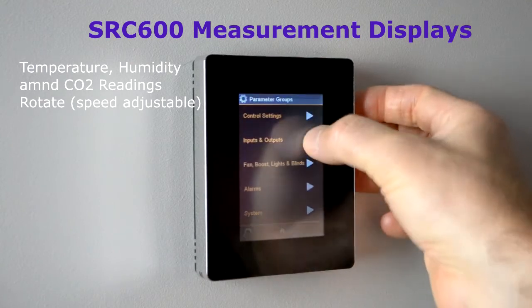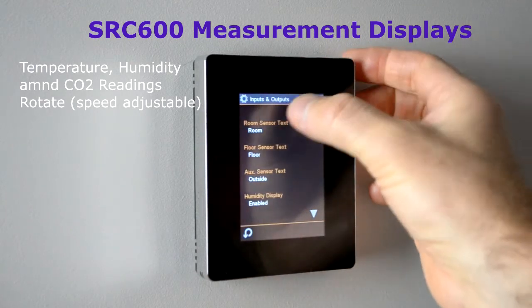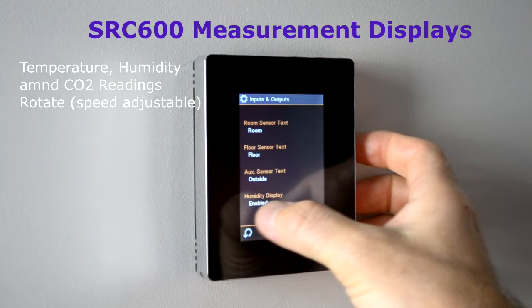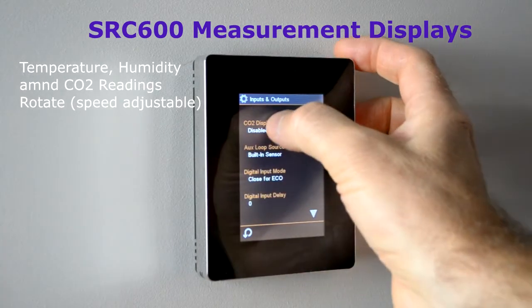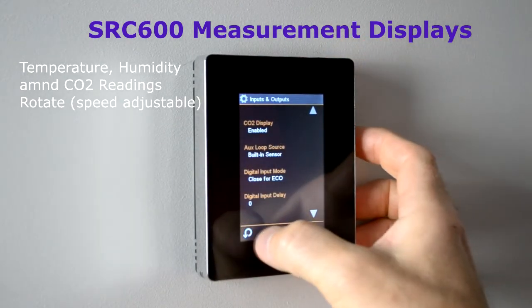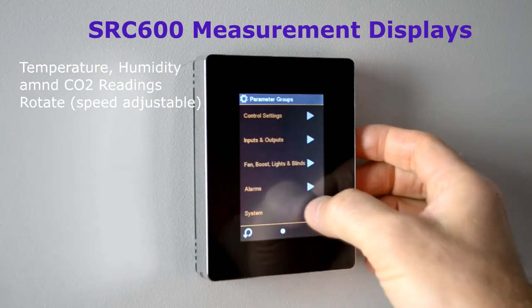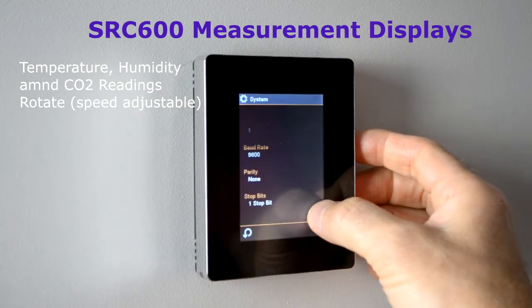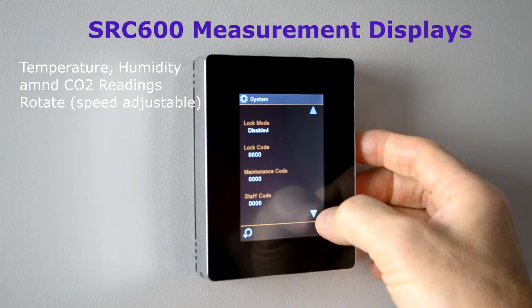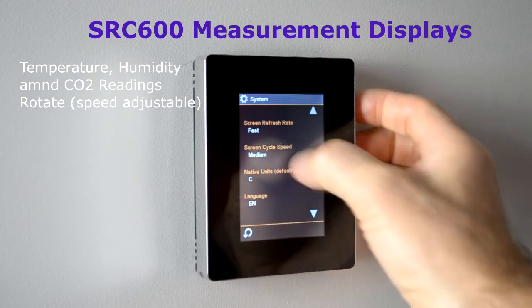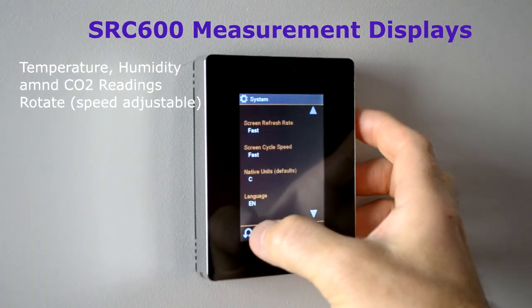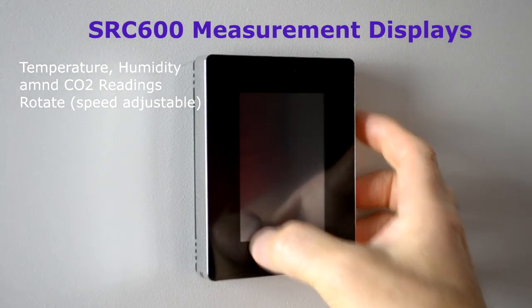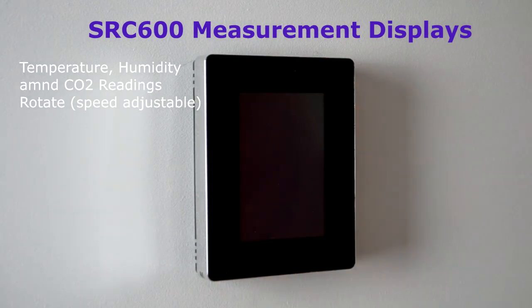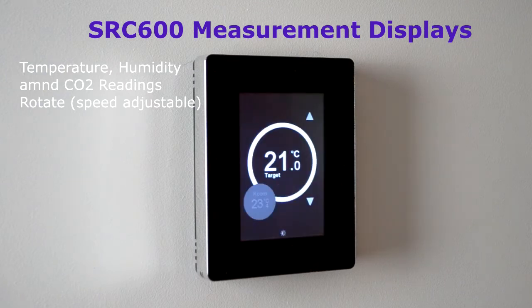So if we go to the settings, in the settings screens, inputs and outputs, there are inputs and outputs menus. Humidity display is enabled, CO2 is disabled. So if I enable the CO2 display, I can also go to the system screen, and I can change the speed, how quickly the screen is rotating. So cycle time is going to be fast. So we go back and return. The unit does a short reboot, and we go back to the front screen.